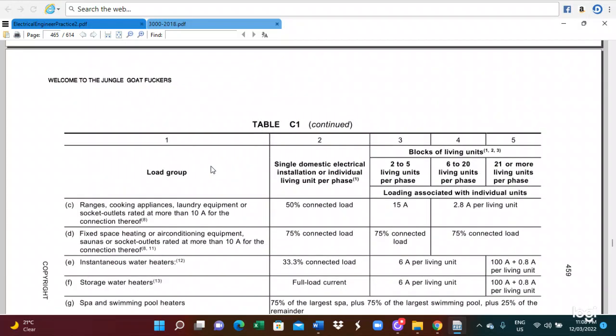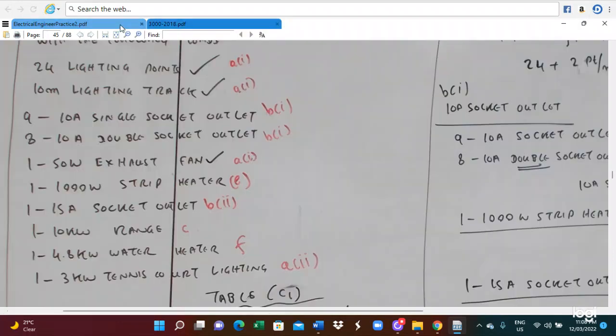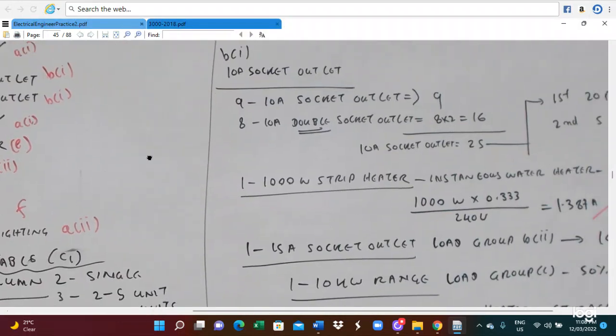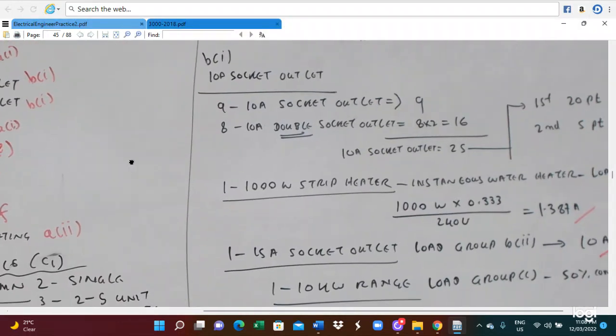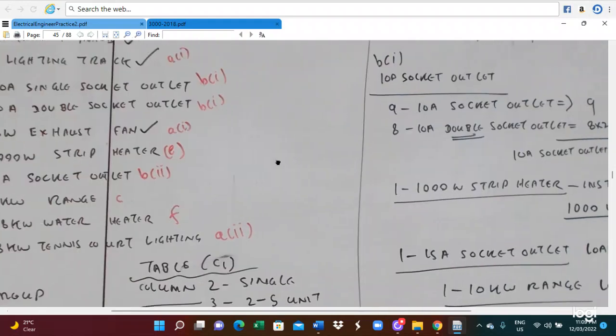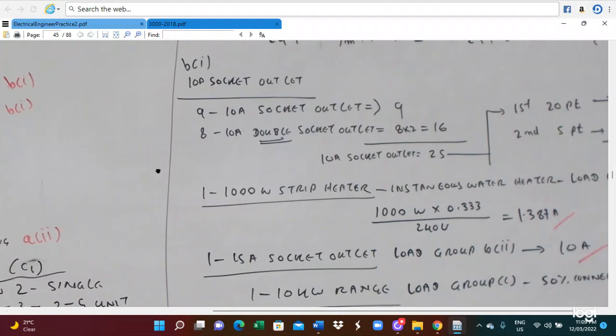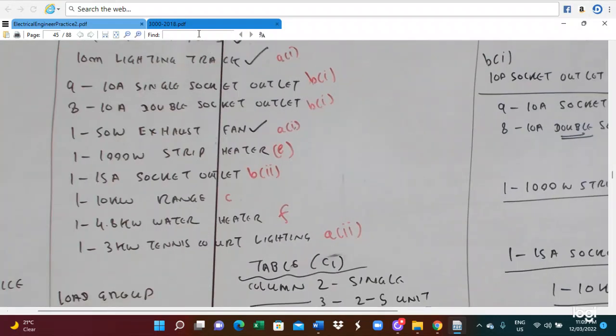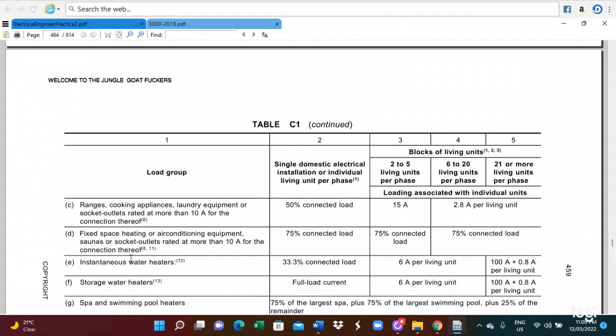So this is for the strip heater. The strip heater is similar to the instantaneous water heater. We can see the rule of the instantaneous water heater here. This is 33.3% of the connected load because the load group is E. Instantaneous water heater is similar to strip heater. This is the load group E.